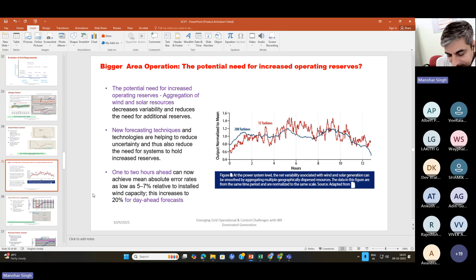Rather than a 15-minute window, if I decrease the economic load dispatch window to 5 minutes, the error will be lesser. So these are new operational strategies: running in a bigger pool, shifting planning from one day ahead to one hour ahead, and reducing the 15-minute window to 5 minutes—or why not 1 minute? But that becomes very cumbersome, since in 1 minute you have to coordinate, run the algorithm, sell power, and take decisions. Five minutes is more practically feasible, and in the US there are pilot projects where this 5-minute ELD window has been tried successfully. So these are the opportunities in that way.